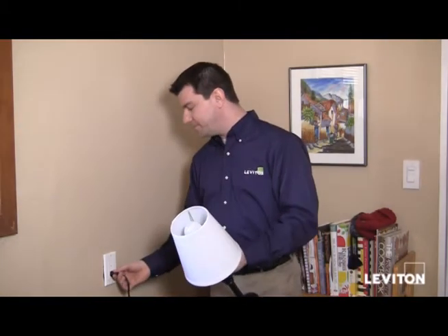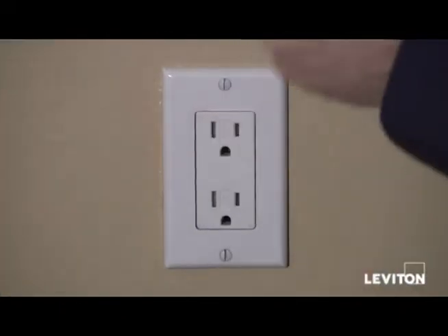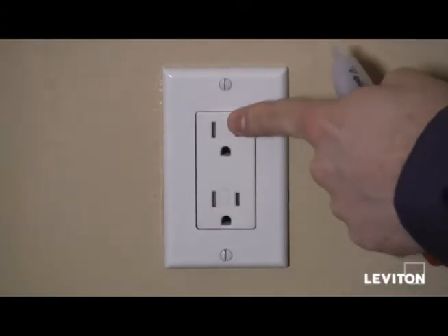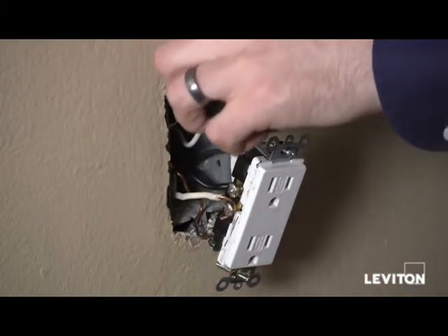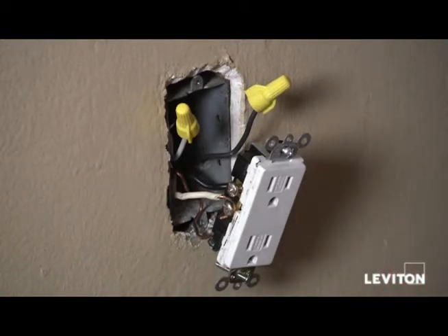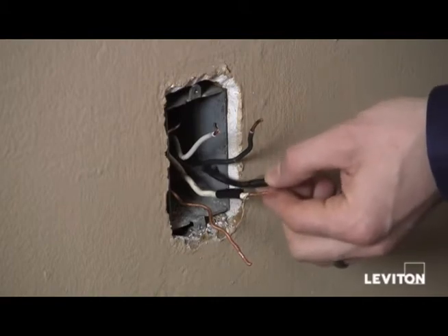Now I'm going to go back to my breaker and shut the power off. I've shut the power back off, and taking my handheld tester, I still want to check to make sure the power is off at the outlet. So I've gone ahead and pulled the outlet out of the box and pulled my two line wires out. I'm going to disconnect the two wires attached to the device and put a piece of tape around the wire so that I know they're my line wires, my power wires. I've removed the old receptacle and taped my wires that I denoted were my line wires.